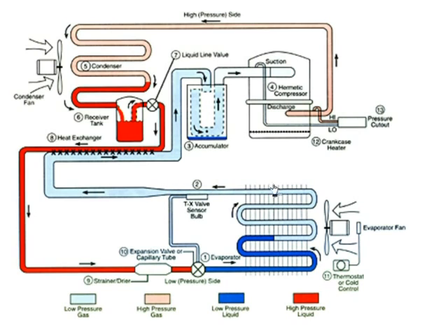Alright, I've used the... subtract 35 degrees from your return air. And you want to measure your return right at the furnace. You measure your return air right at the furnace, and you subtract 35 degrees. That's usually spot on.